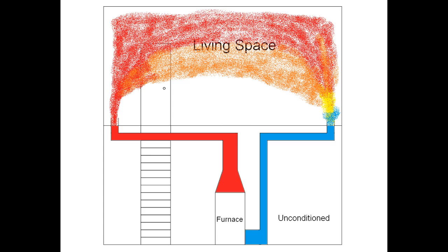And it may not be circulating long enough. An example is an oversized system. If the furnace is too big for the space, it's going to short cycle. It'll satisfy the thermostat by providing heat quickly, but the fan doesn't run long enough to circulate the air throughout the room and make the whole building comfortable.